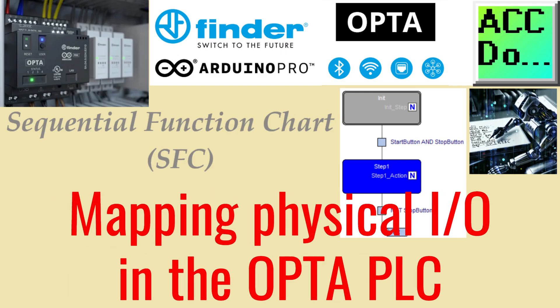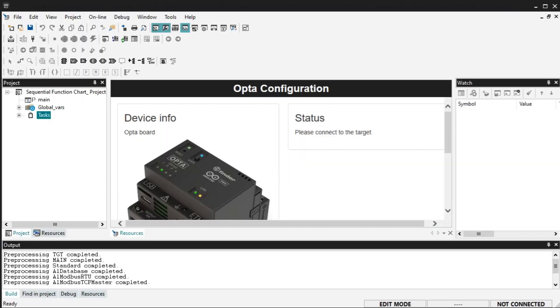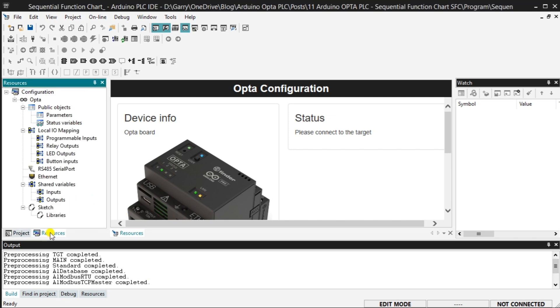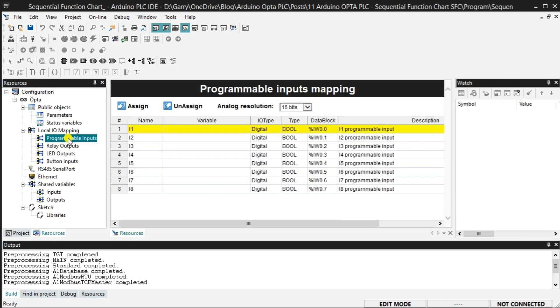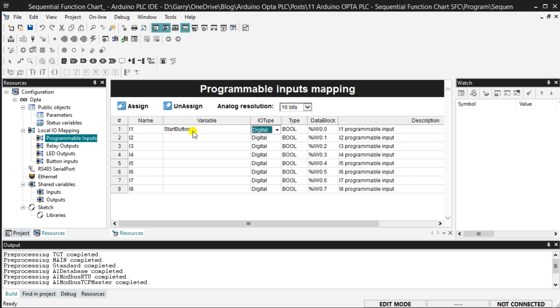The Opta has physical inputs and outputs we must map before using them in our project. In the workspace window, select the Resources tab at the bottom. Under Local I/O Mapping, you will see all of the physical inputs and outputs on this controller. Select Programmable Inputs. The Programmable Inputs mapping will be displayed. We can assign a variable to each input we intend to use in our structured text program.